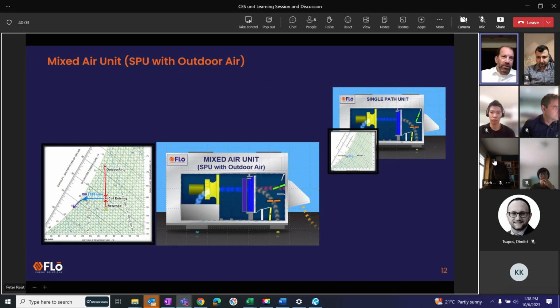What we're trying to achieve is a store that is sitting at between about 50 and 52. That's the dew point temperature of the store. That's what we want because we want to be below the 55, which is the high limit for refrigeration equipment. So we drive our coil really cold. We get as much moisture as we can, and then we get it back up.